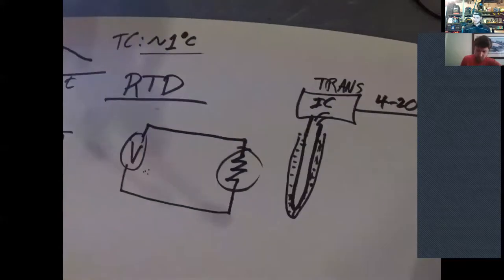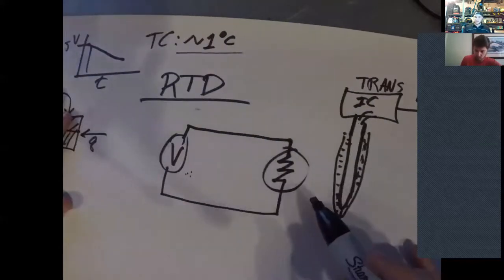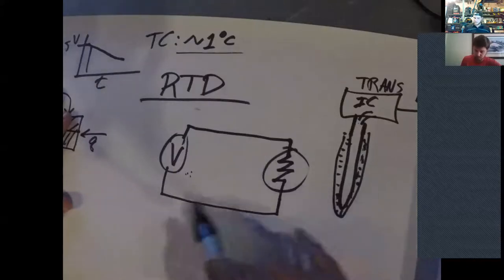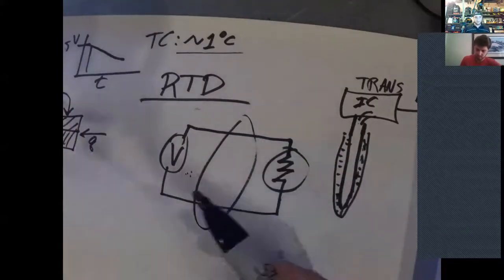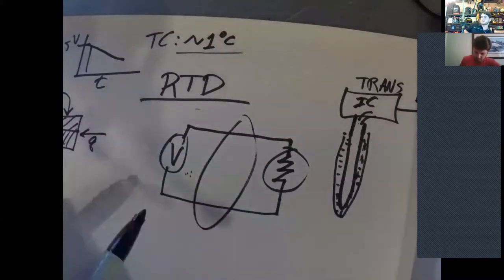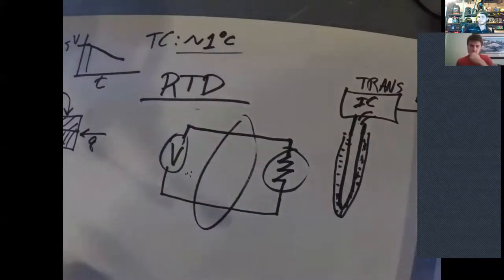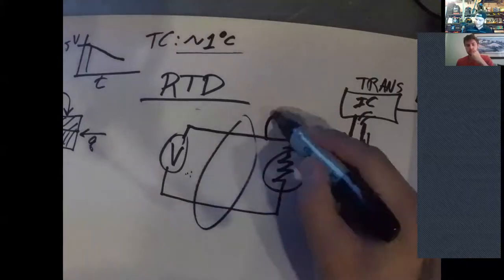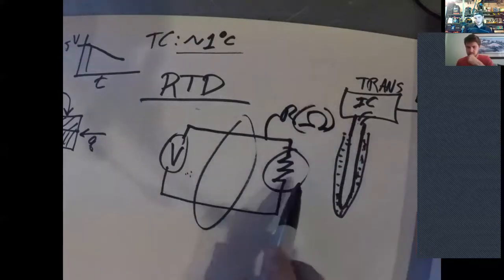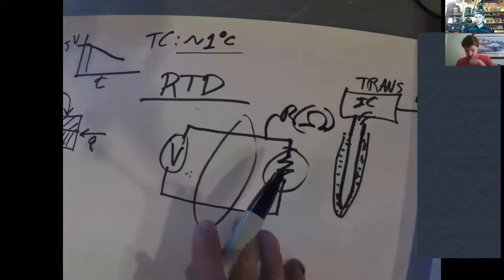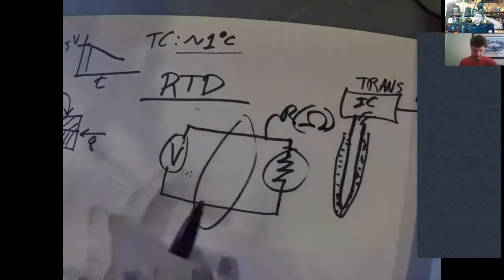So then usually the RTD has an integrated circuit board that has basically a signal transducer. So it reads that voltage, changes that into a 4 to 20 milliamp signal. That analog signal goes back to your controller. So this is more common in permanent installs and processes, you'll more than likely see RTDs and not thermocouples for measuring temperature, just because it gives you a much higher degree of accuracy.